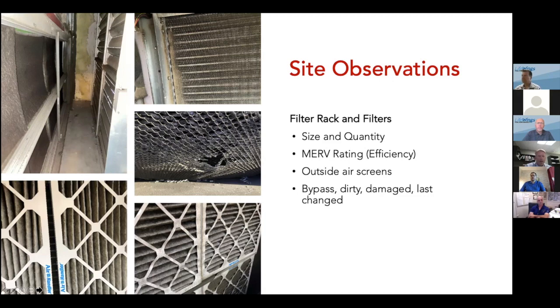The biggest issue we saw is the dirt, NOx emissions, and brake dust, or just general outside air, and I'll talk to that in the next slide on air quality. The filters obviously load up very quickly. You can see in the upper left they're actually being sucked in because they're loaded up. But the biggest issue that we see is bypassing. The bottom left photo is filters that don't fit tightly in the filter rack.